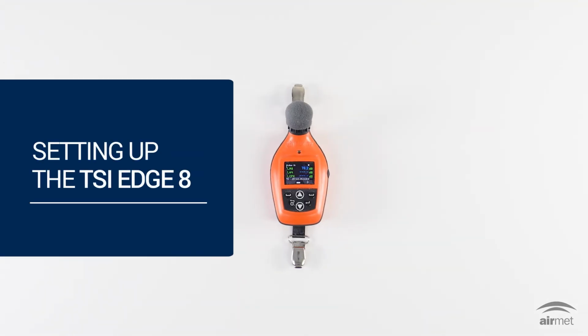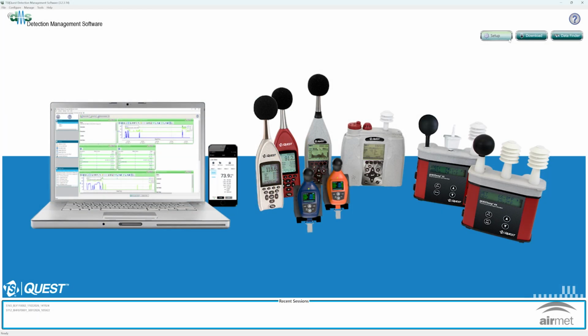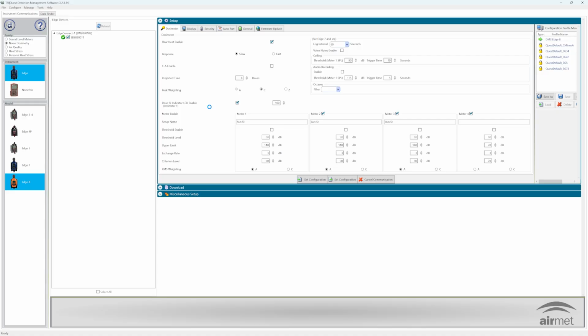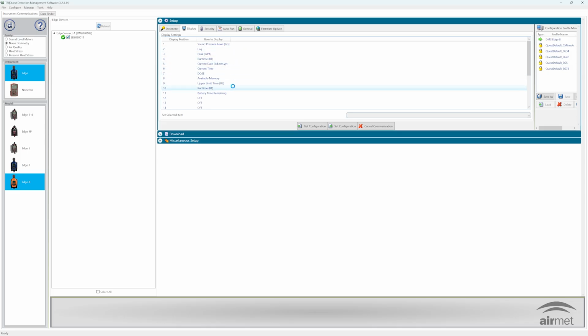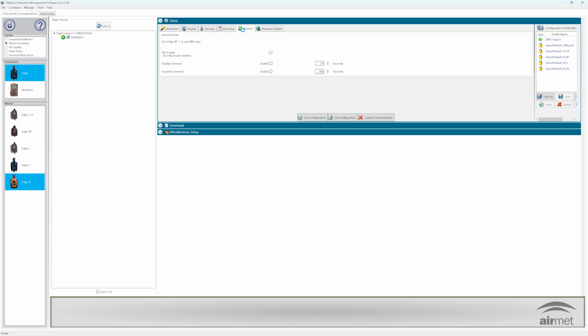Setting up the TSI Edge8 requires the use of the TSI Detection Management Software, or DMS. This is required to configure parameters like criterion level, threshold, exchange rate, and measurement duration. Up to 4 virtual dosimeters can run simultaneously. Through the DMS software, you can also enable features such as octave band analysis, auto run, and audio recording.